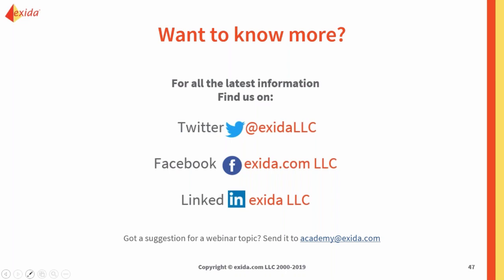So the easiest way I say to look up devices if they're SIL capable or not: on the exida website, there's a link called the SAEL, and that has all of the certificates, and you can look up logic solvers, and you can say, I need a SIL 3 logic solver, and it will pull down all of the SIL 3 logic solvers for you. You can look at their certificates, look at the companies, look at the failure rates, and see which one could work best for you.